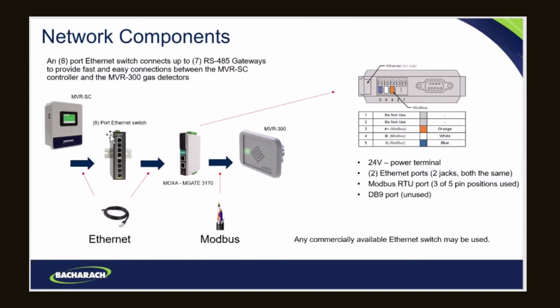Larry was just pointing out that both this Ethernet switch and the gateway will have some sort of power need. Typically these are plug-in wall warts that you just plug in. They're 24 volts or 12 volts or whatever the internal voltage is. Yeah, they usually come with a power supply, correct? Yeah, typically they will. And like I said, the Ethernet switch you can go buy off the shelf someplace. We've got some specifications around this converter, and a little more detail that we'll share with you regarding the configuration. You can go to Best Buy and get Ethernet switches too. Well, we'll probably just spec that Moxa. Right. And we give some configuration advice around the Moxa converter as well.